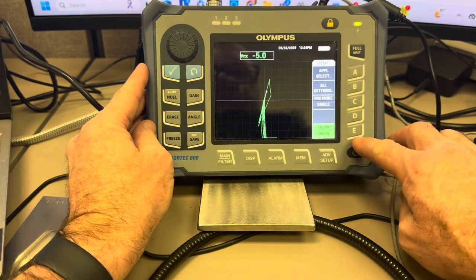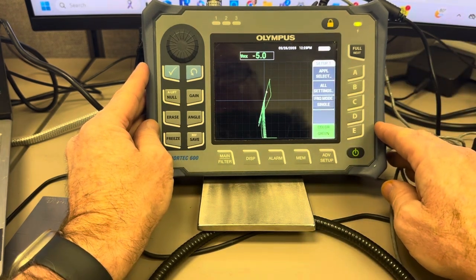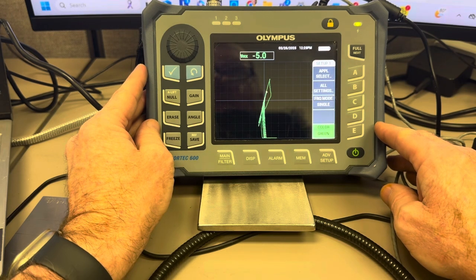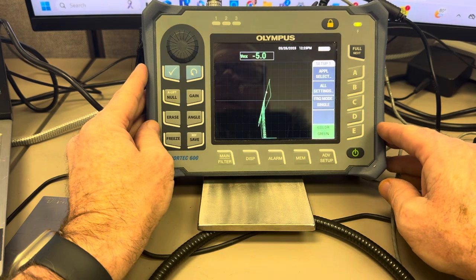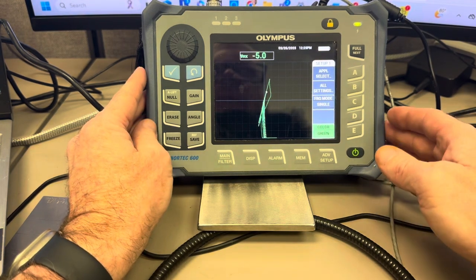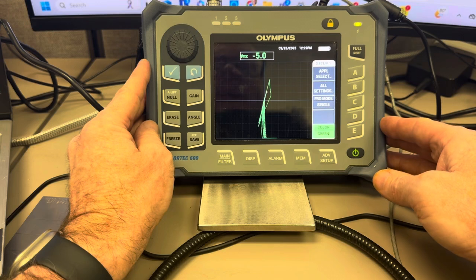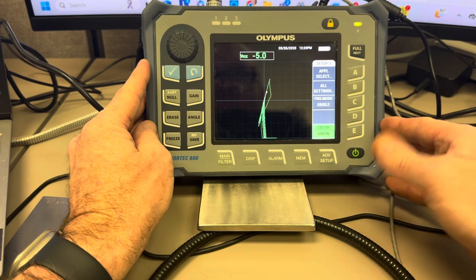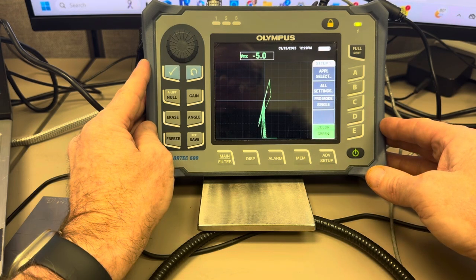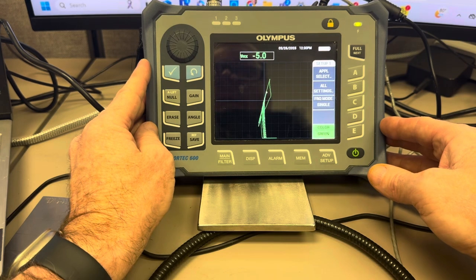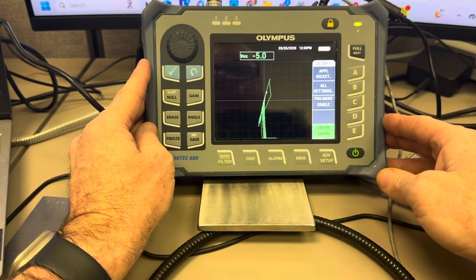So that's basically it. Now there's a lot of features that you're not going to use commonly. You know, you're going to use just a lot of the basics over and over again. If you want to know how specific features work, for example, if you wanted to set up a bolt hole standard with a rotating scanner, that's something you probably don't do that often. So you're going to need to refer to the instruction manual and go find out exactly how to set it up. That's one thing about the Nortec 600 operator's manual, is it teaches you how to set up the instrument for just about every type of test that you can do with it. So that covers the basic functions of the Nortec 600 flaw detector, and we'll get deeper into the settings and test applications in further modules.